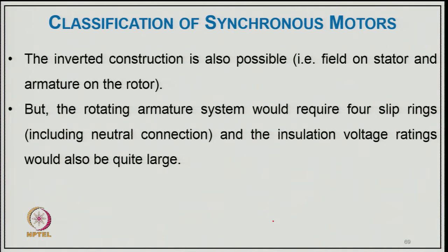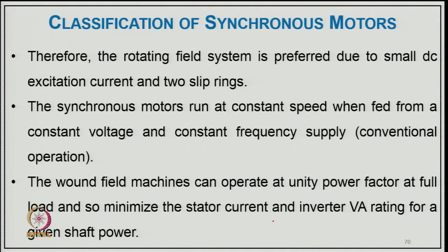So, the inverted construction is also possible, meaning field on the stator and armature on the rotor, by principle. But the rotating armature system will require 4 slip rings including neutral connection, and the insulation rating will also be quite large. Therefore, the rotating field system is preferred due to small DC excitation current and 2 slip rings.